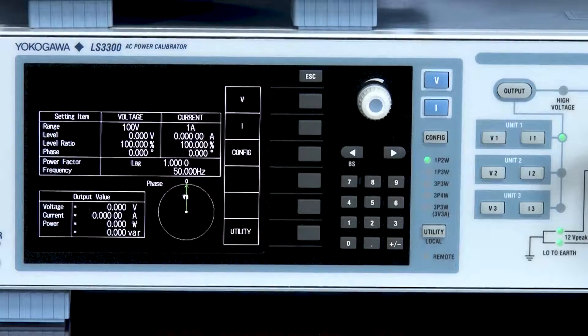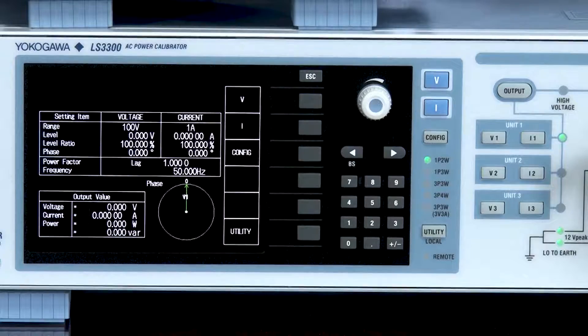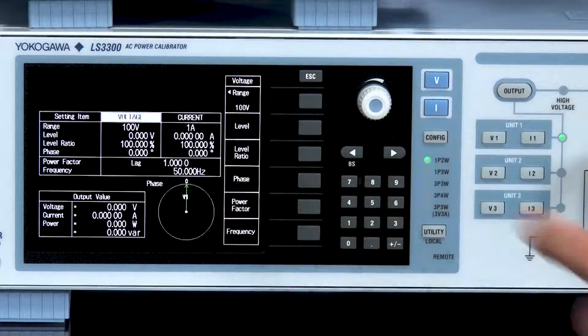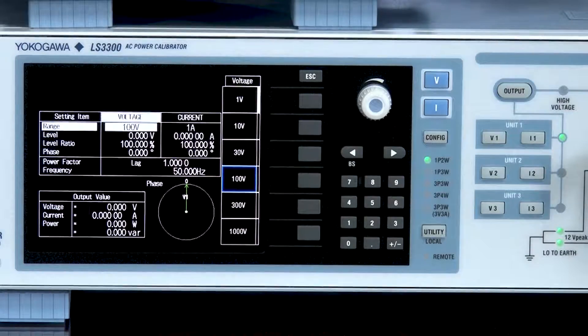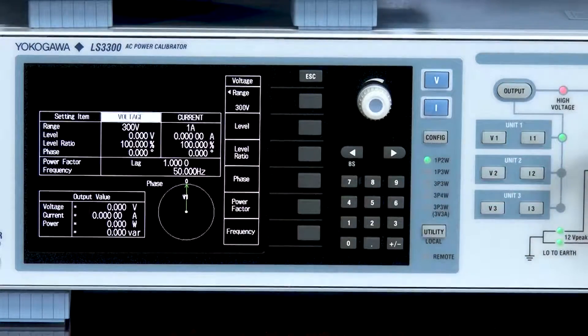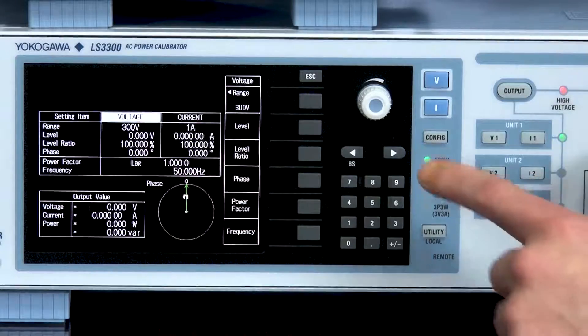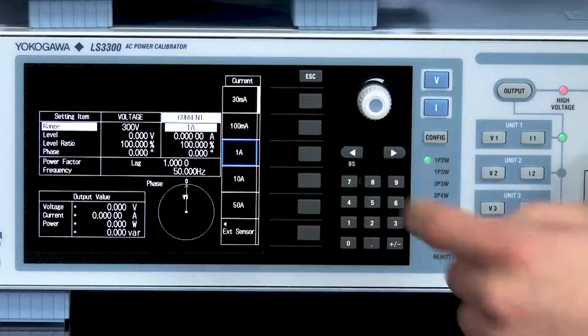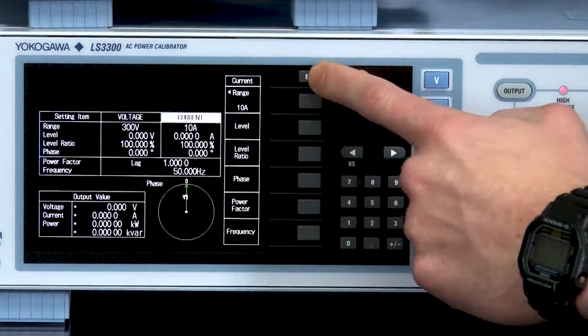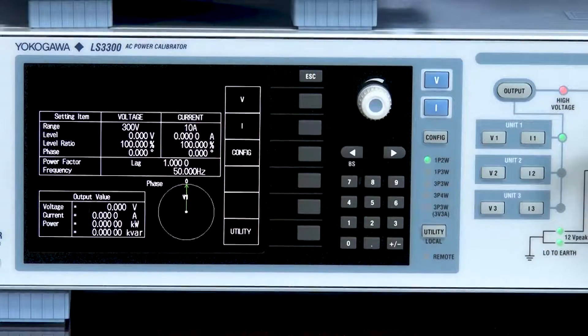Next step would be to set the voltage and current ranges. To set the voltage range I'll press the voltage button followed by select range, and then for this test we will use 300 volts. Similarly for current, I will select the current button, select range. Next I will select 10 amps for this test and then we can exit back out to the main menu.